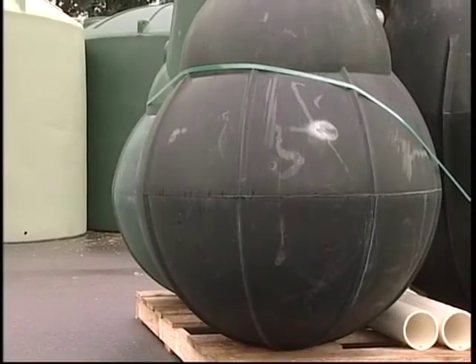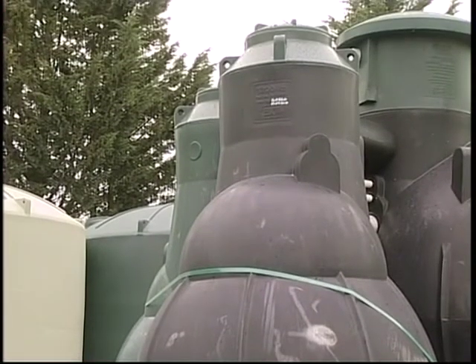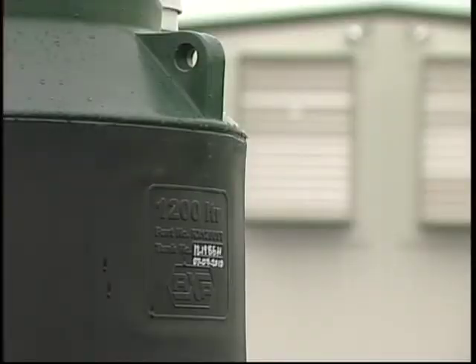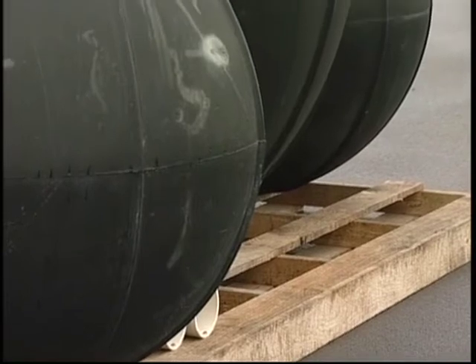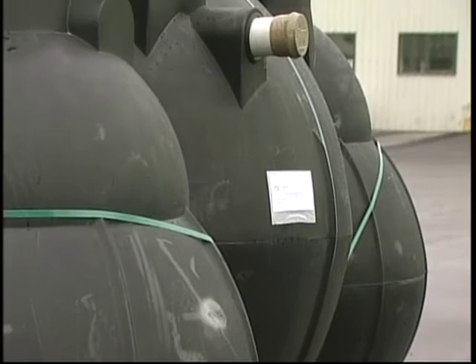So we call that an aerobic breakdown happening there. It hydraulically transfers into the next chamber — a clarification chamber, a settling pond, in simple terms. All the particles from that dirty water settle into the bottom of that chamber. Then we have a pipe in the bottom of that chamber called an air venturi lift pickup. It sucks off the bottom there, all the sludge, and returns it back into the primary, the first chamber, for retreatment.